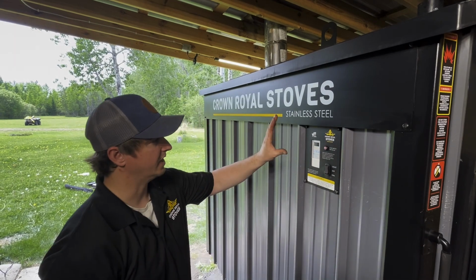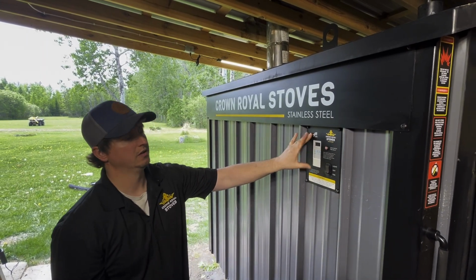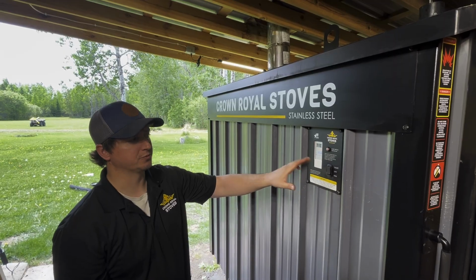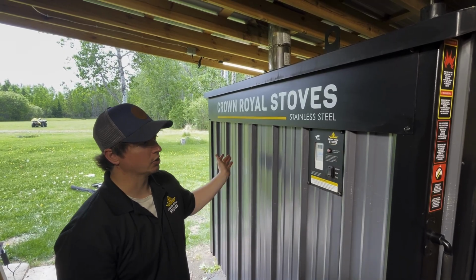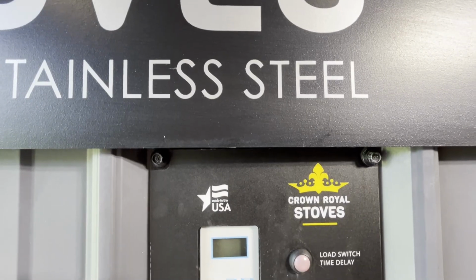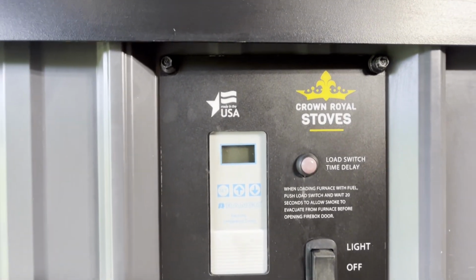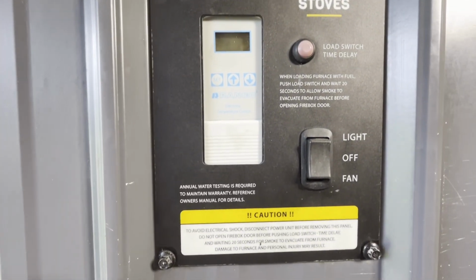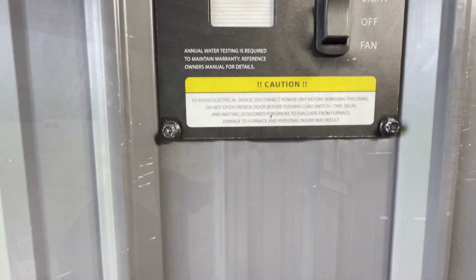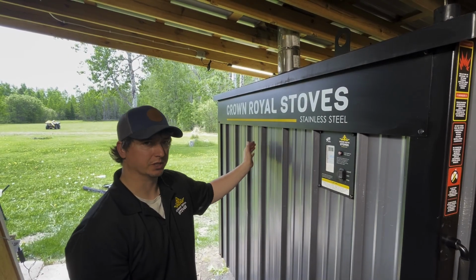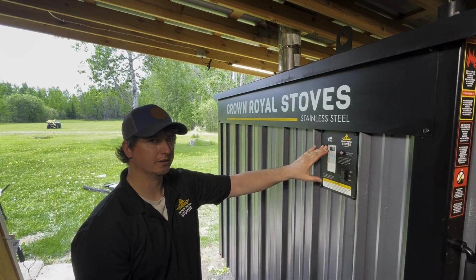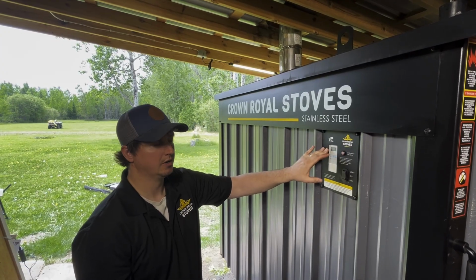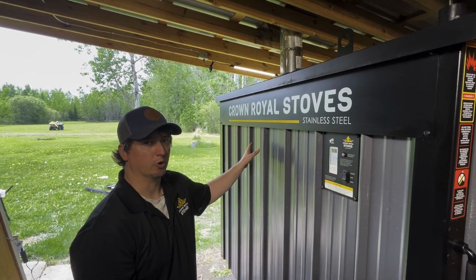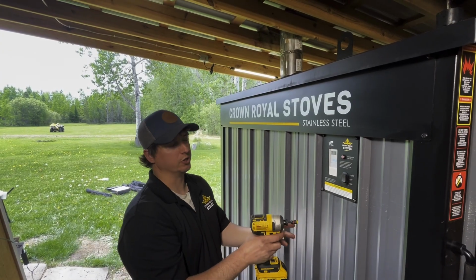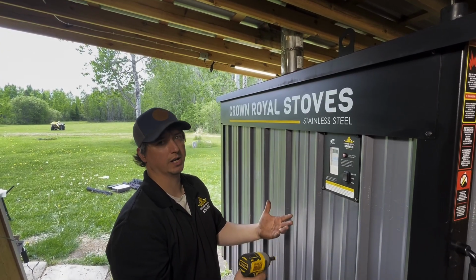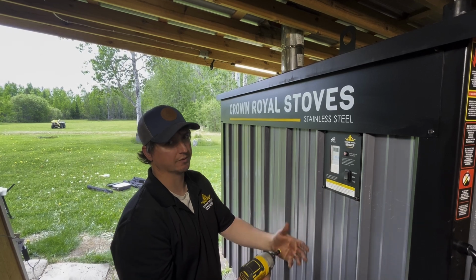And that's it, that is how you switch out your Aquastat. The same process would apply if you were switching from a Ranco controller to a new Ranco controller. The only difference is, if you'd like, you can use the old probe, as long as you know for sure the problem wasn't the probe. So if you were just having a display issue with your Ranco controller, you're welcome to leave that probe in there, but that would require you to take the Aquastat apart and wire the old probe into the new Aquastat.